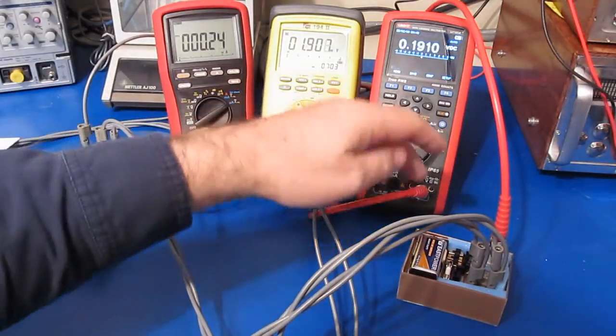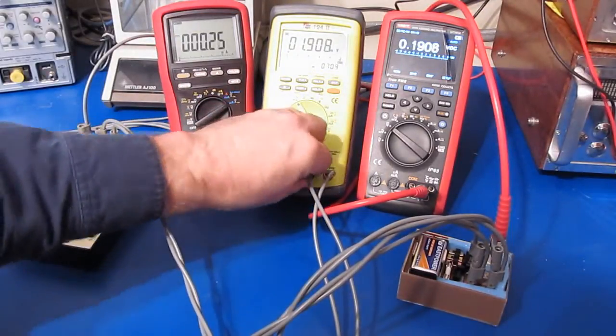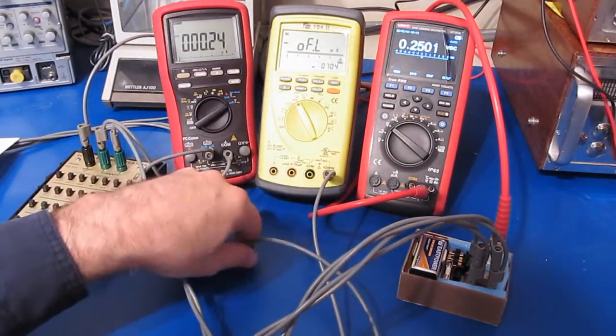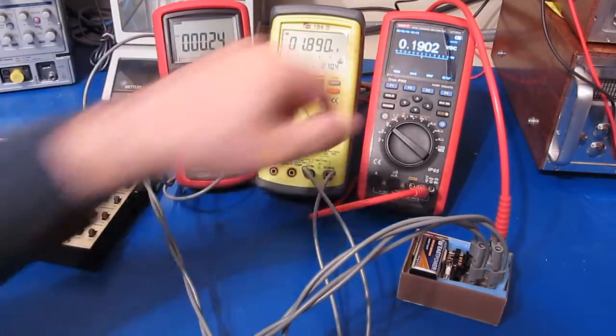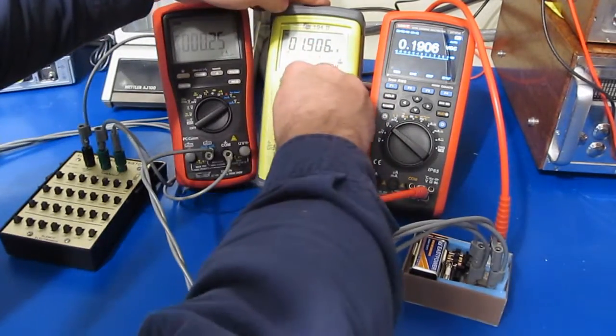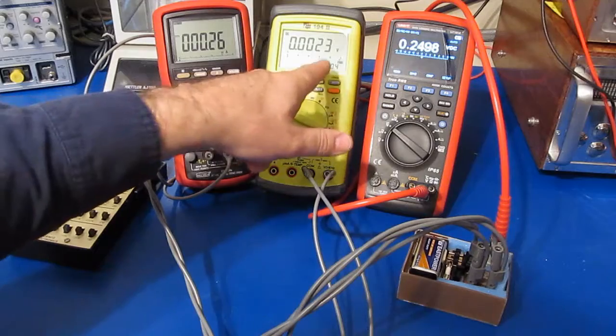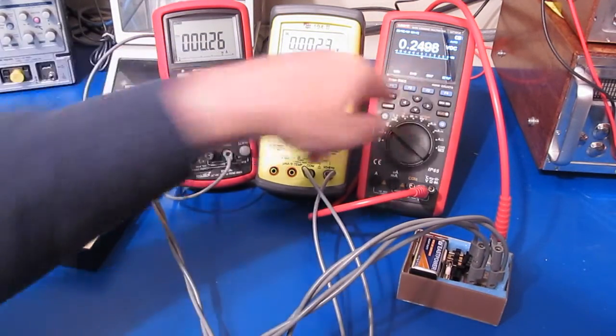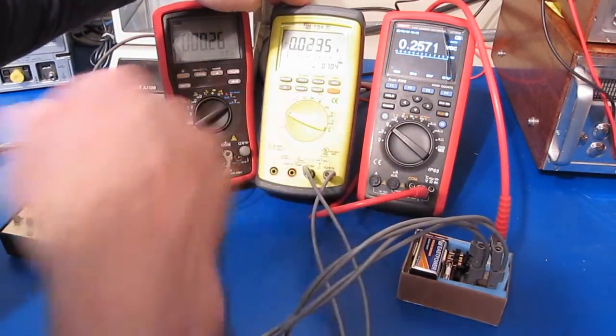The problem here isn't actually this box — it's the loading of this TPI 194 across it. If I remove the input to this, look: 0.2501. Reattach the meter and it loads it right down. What we can do is change this meter over to the voltage input — that will increase its input impedance, and now you can see it's having much less of an effect — basically no effect.